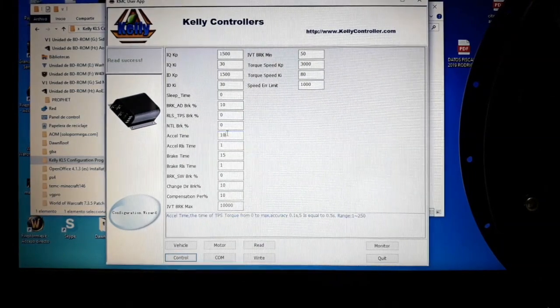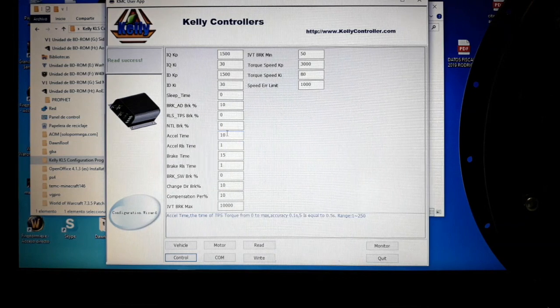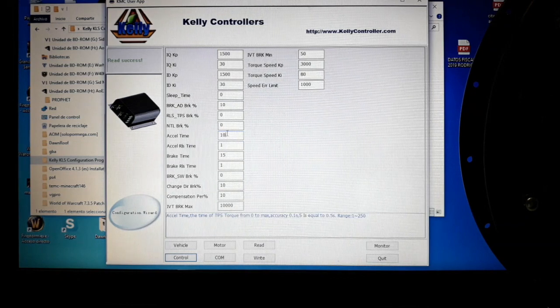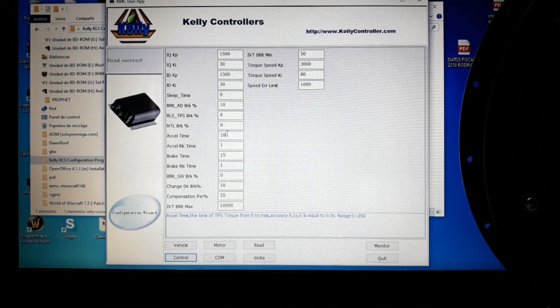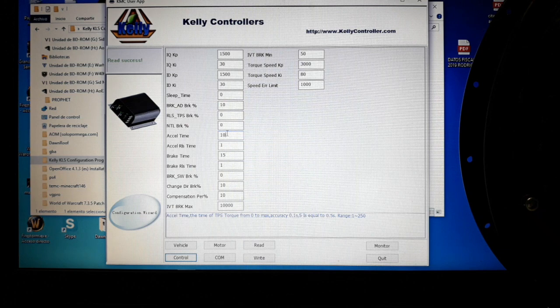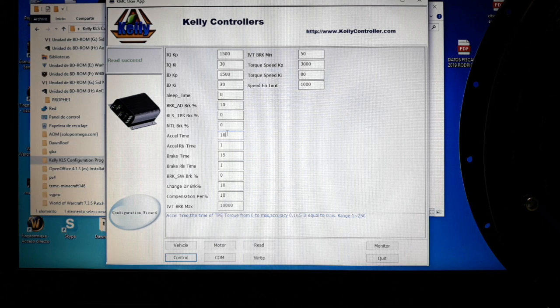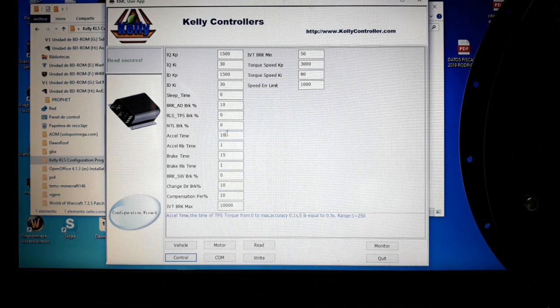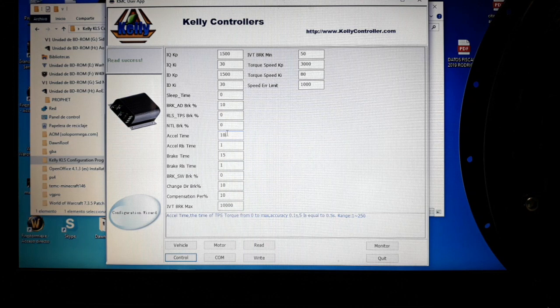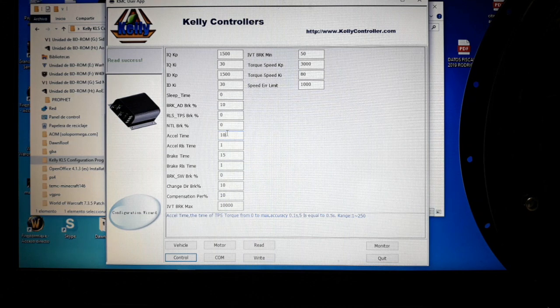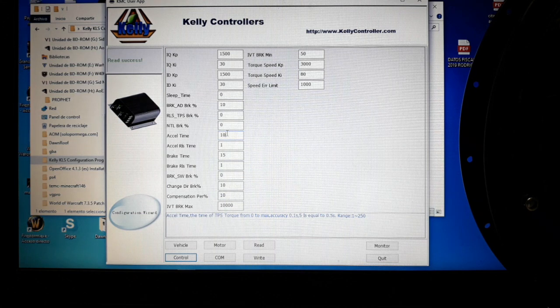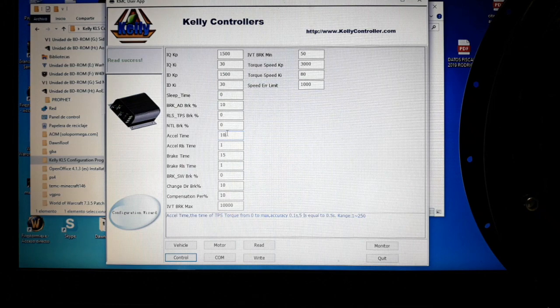The next one is acceleration time. This setup delays a little bit the acceleration. What it means is that it will delay a little bit from going from zero torque to maximum torque for a while. This is used for two things. The first one is in order to protect all your mechanical components. If you have a transmission and your torque goes from zero to 100, you are able to break something on your transmission. So you can set up here a little delay.